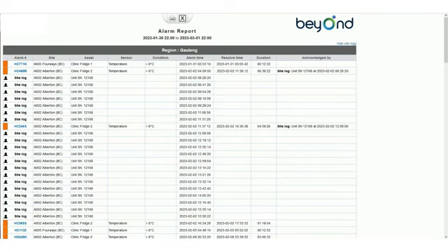If the alarm mute button is pushed on an ICE cubed or ICE cubed extra device, the button push will be logged and made part of the alarm report for any active alarms on that device. All alarm mute button pushes are logged. If an ICE cubed or ICE cubed extra device currently has an active alarm and its alarm mute button is pushed, the button press will be linked to an alarm event and the alarm will be marked as resolved with an orange icon. If an ICE cubed or ICE cubed extra device currently has no active alarms, but its alarm mute button is pushed anyway, the button press will be logged but will not be linked to an alarm event.